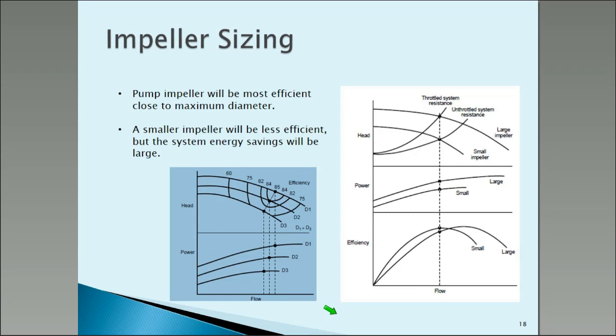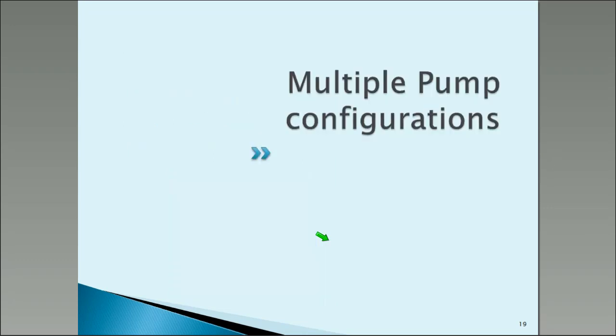One thing you can do — and you don't see it very often because there's no going back — is put in a slightly smaller impeller. This is your pump as you bought it; with a smaller impeller you've got a bit less head. The efficiency may fall just a little bit, but the power can fall quite a lot. The amount you save on system energy consumption can be much more than what you lose on efficiency. The problem is once you've trimmed your impeller and put in a smaller one, it can be hard to go back to a bigger impeller.